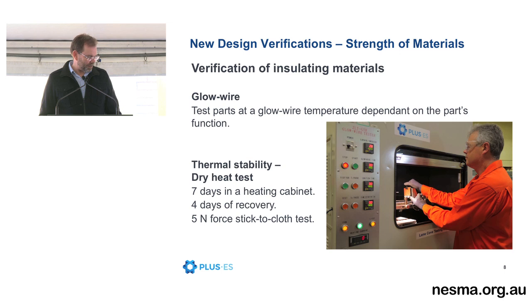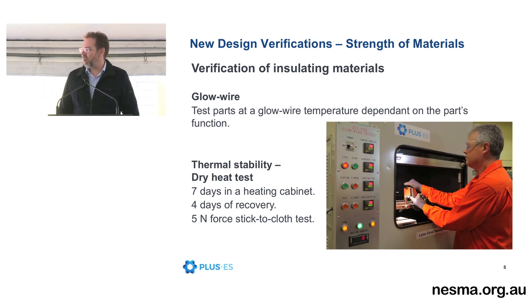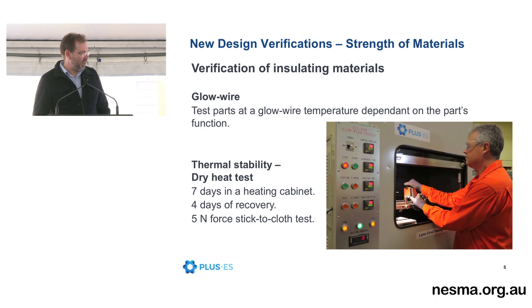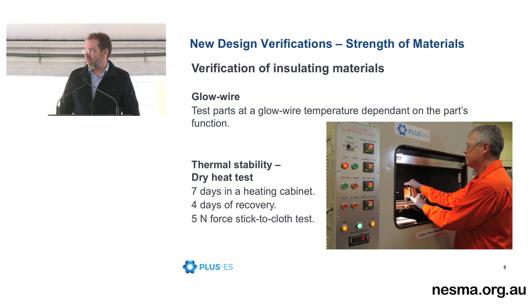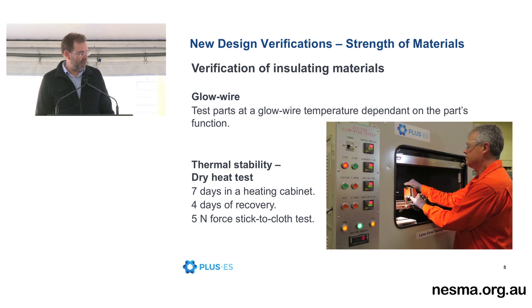Insulating materials, verification of those. Insulating materials is a fancy word for plastic. So if you have a piece of plastic and it's forming part of your enclosure, you have to do a thermal stability test. If you have a piece of plastic and it's holding up a bus bar, or it's preventing you from touching a bus bar, then you need to do a glow wire test on that.